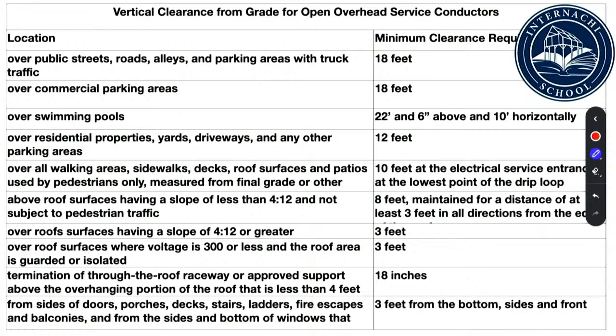Above roof surfaces having a slope less than 4/12 but not subject to pedestrian traffic. All right, and that's where that inviting people out there is. 8 feet. Roof surfaces having a slope 4/12 or greater, 3 feet. And then again, that has to do with a separate building. Over roof surfaces where voltage is 300 or less and the roof area is guarded or isolated, that's 3 feet. And that comes into play in the city of Chicago a lot. Termination of through the roof raceway or approved support above the overhang portion of the roof that is less than 4 feet, and this is kind of what I was trying to draw earlier, that can get within 18 inches.